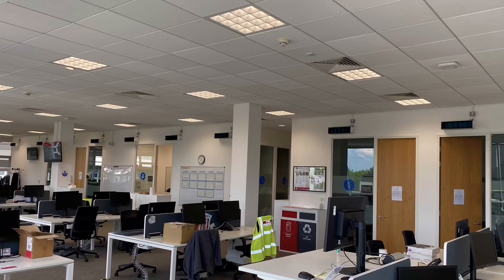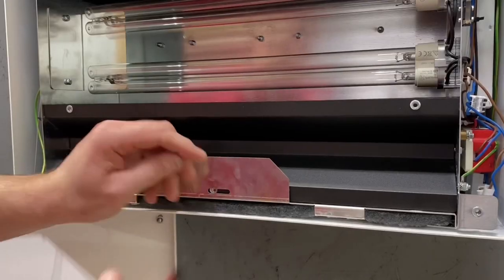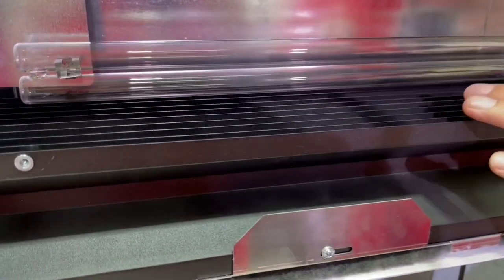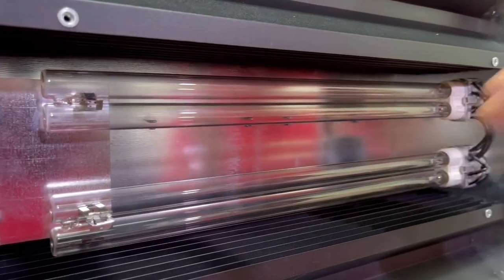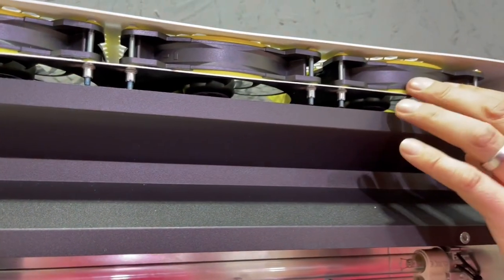I've left it exposed because hopefully you'll do a deep dive for me. So we've looked at Philips' UV disinfection solutions for air before on the channel. The difference with this one is it uses fans to force the air through the unit and expose it to UV light. The air enters on this side of the unit, passes through a filter to remove dust — the filter's really easy to change, every 4,500 operating hours — and then it passes through this clever chicane so that the UV light can't leak out from the unit. Once through there, the air is exposed to the UV tubes: two 60-watt tubes, which disinfect and inactivate any viruses or nasties. Then the same on the outlet side — this clever chicane again, and fans at the top that deliver up to 120 metres cubed of air flow per hour.